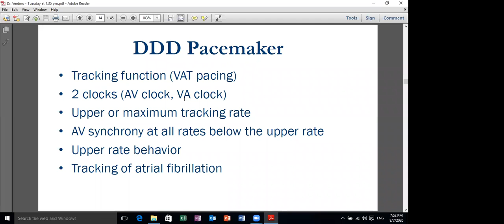So this is the dual chamber pacemaker. At the top here we have an ECG. In the middle we have an atrial electrogram because this is a dual chamber pacemaker. And below it you have a ventricular electrogram. Here we have a sensed ventricular event. We program a lower rate limit here as 60 beats per minute. We program an upper rate limit depending on the age of the patient and the comorbid conditions.